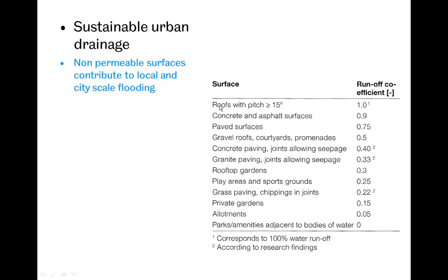So right at the top, we've got roofs. Building roofs with a pitch greater than 15%, runoff coefficient of 1. So in other words, all of that rain which hits that roof runs off very, very quickly. There's no absorption and there's no storing of water. Concrete and asphalt, 0.9. So 90% will flow off, and only that very small 10% is actually held on the surface.